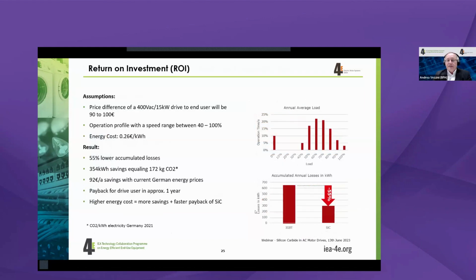Now, you have to take this and look at the mission profile, and this is probably the most important part. If you have a variable speed drive application, we need to look at the different operating speeds and how much time you spend at each. So you see here, this is the operation time over a year. It roughly is between 40 to 100%, with the largest part between 60 and 70%.